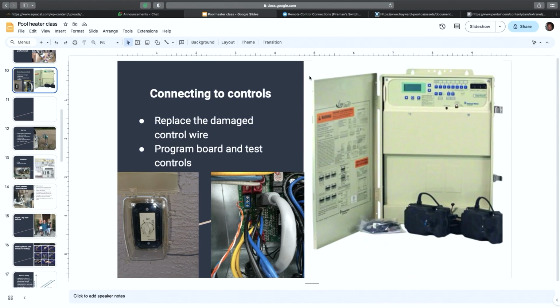So in the off position, what mode are you in? Pool mode. Yep. And so if the pool's not hot, the heater will still run when the dial's on off, because it'll be in pool mode. So you can adjust at the heater what the set temperatures are for each mode. And then all that a guest staying in the house has to do is turn that dial. And what else does the dial activate? The actuators and blower. If they have a blower for the spa, which pretty much everybody does, it also activates the actuators.